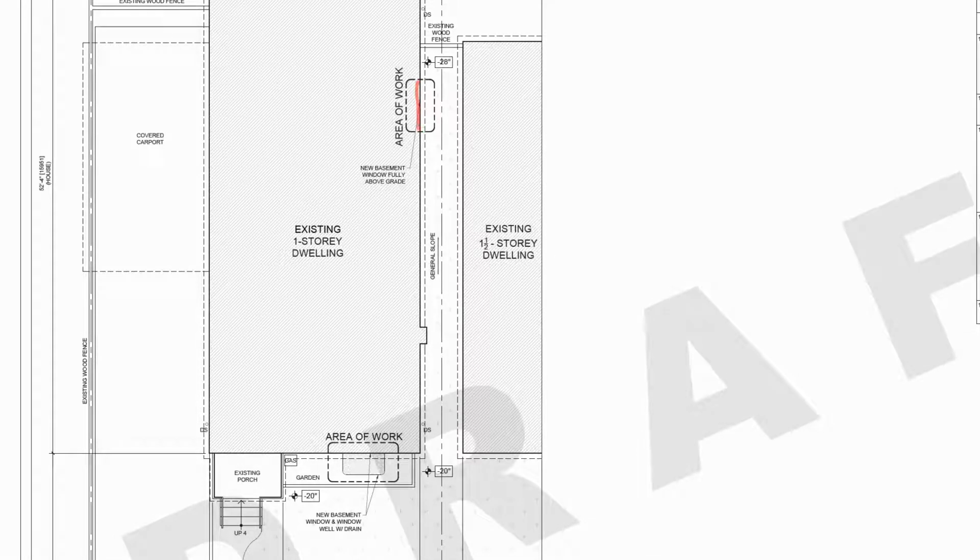So we still could put a window in here, same size and everything as we've had shown, and as what is shown in your quote from the contractor. However, there would be some additional things. We either have to do a fire rated window with a 1 hour fire rating, so that it won't break right away if there's a fire, and it'll save this neighbor's building. Or we can do a fire shutter over the window, which is a mechanism that will activate if there is a fire, and roll down and cover the window to prevent that flame spread again. So it's not to say we can't do a window there. There's just a couple things we'd have to do.